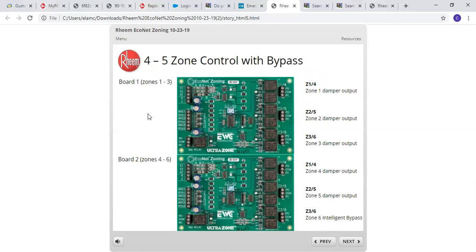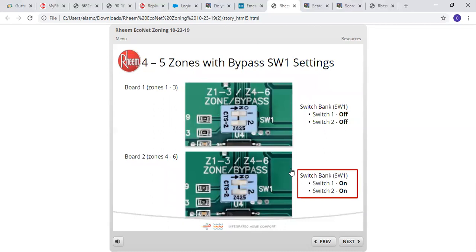Now, if we're going to do a 2-board system, a 4 through 6 zone with a bypass, here's where it gets kind of important again. Once again, on the zone 1 board, our dip switches are going to remain off in both cases. Since we're going to use zones 4 through 6 with a bypass, we not only have to turn on 1, which indicates we're going to use zones 4 through 6, but we're also going to turn on dip switch 2, which indicates we're using a bypass. And then bypass will be used on number 6.